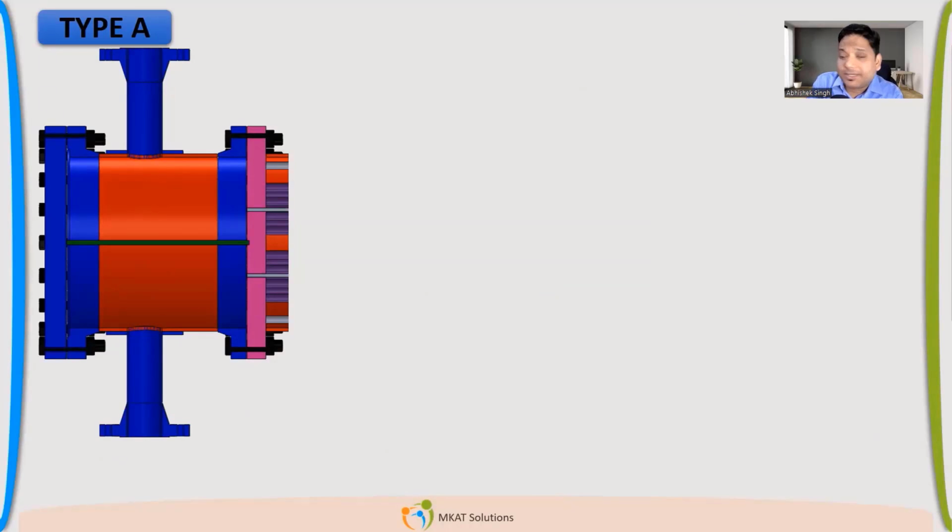see all the heat exchanger, the front side, there will be channel. Okay. There will be tube sheet, there will be shell in the middle, then at the rear end also maybe channel, maybe cover. Okay. So how these items are attached, based on that, the type varies. So here you can see there is a blind flange attached to the channel. So channel attached with a flange, and then there is blind flange. Okay, so it's a removable cover.